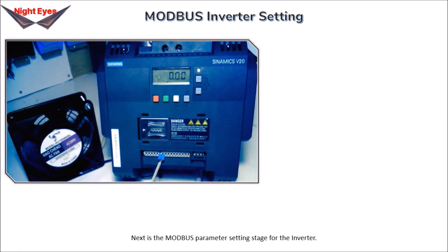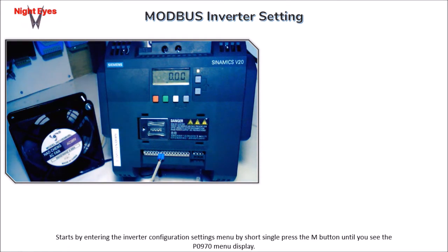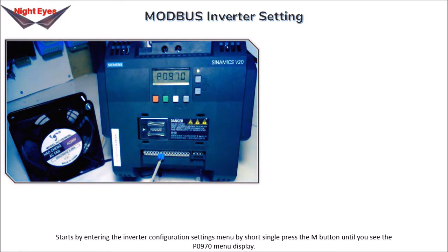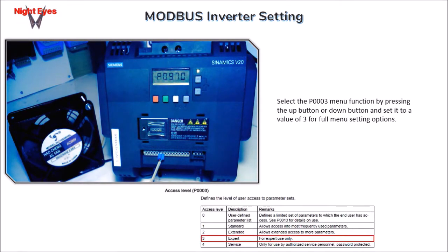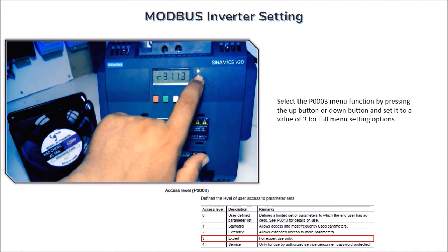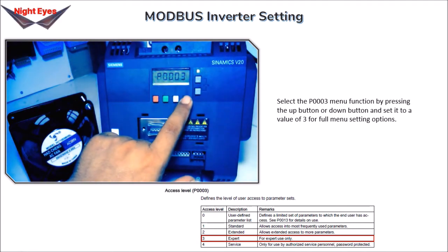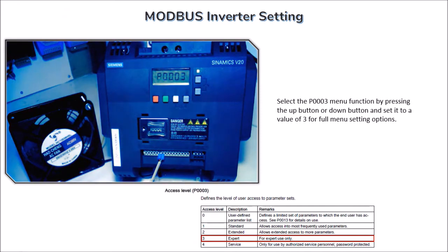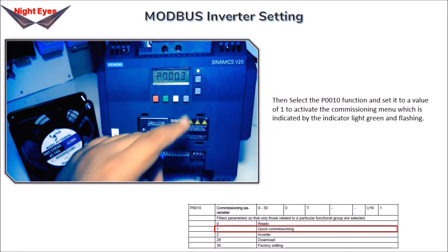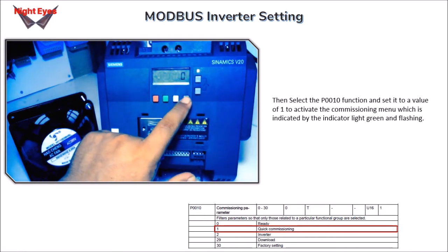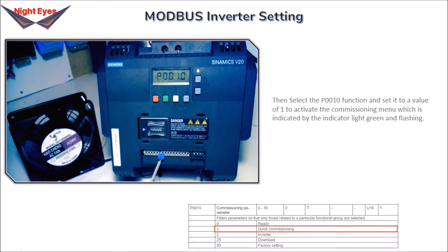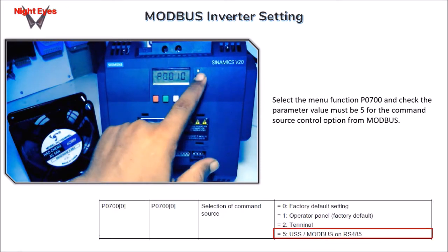Next is the Modbus parameter setting stage for the inverter. Enter the inverter configuration settings menu by short pressing the M button until you see the P0970 menu. Select P0003 and set it to 3 for full menu setting options. Then select P0010 and set it to 1 to activate the commissioning menu, indicated by a green flashing indicator light. Select P0700 and verify the parameter value is 5, for command source control from Modbus.